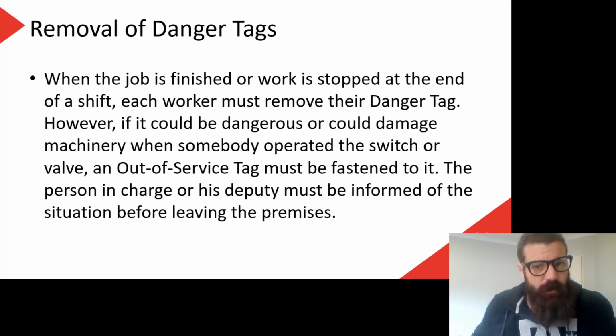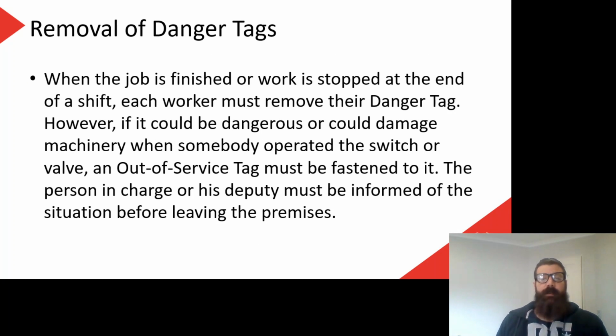Removal of danger tags. When the job is finished or work is stopped at the end of the shift, each worker must remove their danger tag. However, if it could be dangerous or could damage machinery when somebody operated the switch or valve, an out of service tag must be fastened to it. The person in charge of this or their deputy must be informed of the situation before leaving the premises. Yeah, that sounds very formal. It's probably an informal thing. You just let somebody know on site, I've still got this tagged out, it's still switched off. If you don't swap your danger tag for an out of service tag, it's not the end of the world. As long as we've got a lock on there and we've got some sort of tag, that's the most important thing.